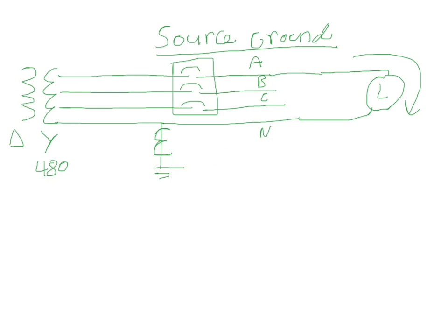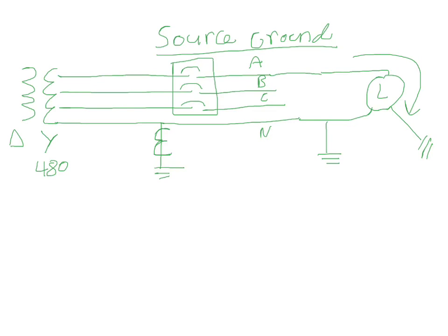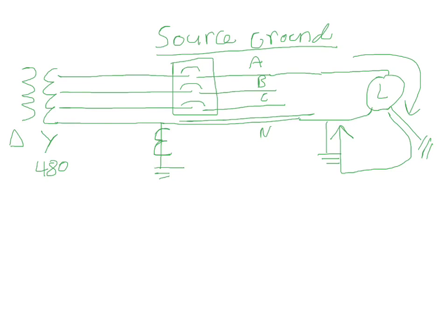Because if it's grounded right here, for example, and then you have a ground fault right here going to ground, it would come to ground here, come back up, and then it would bypass this ground CT and it would run all the way back to the transformer without the system even knowing that there is a ground fault.